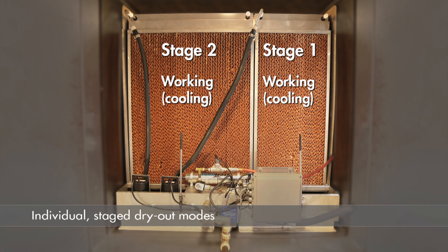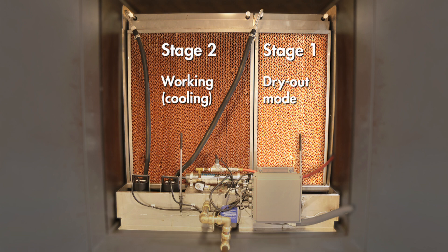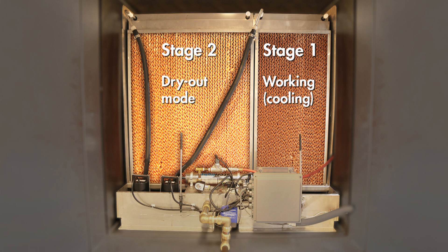Our wetted media system is able to cool constantly. We accomplish this with individual staged dry-out modes. By building multiple, separately controlled stages into the system, we can dry out one stage while the remaining stage or stages are evaporating water and cooling the air.